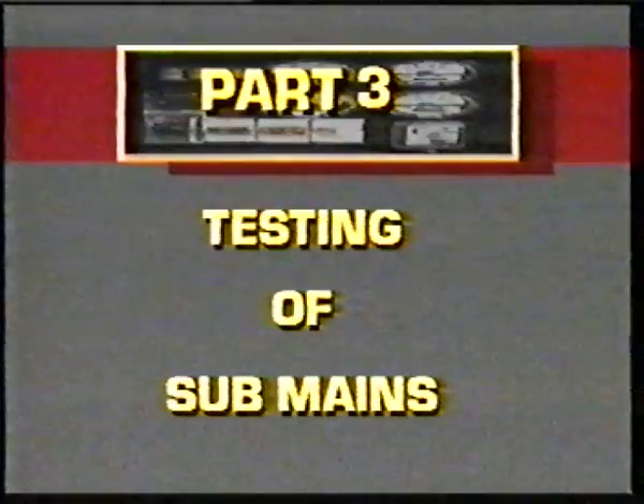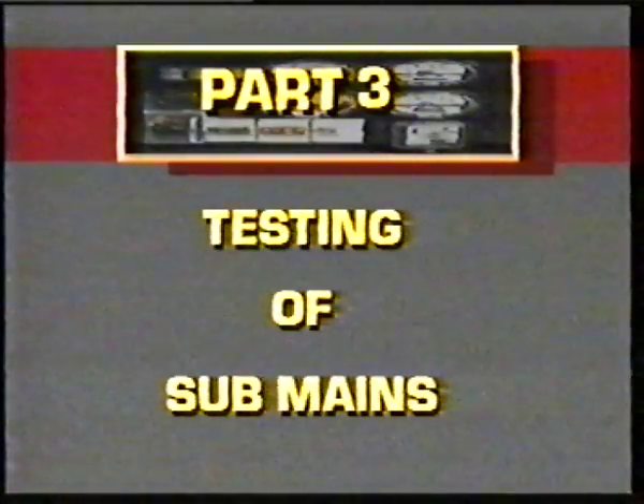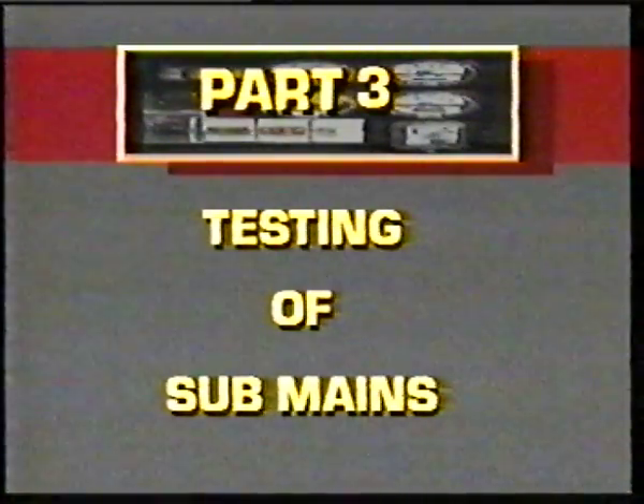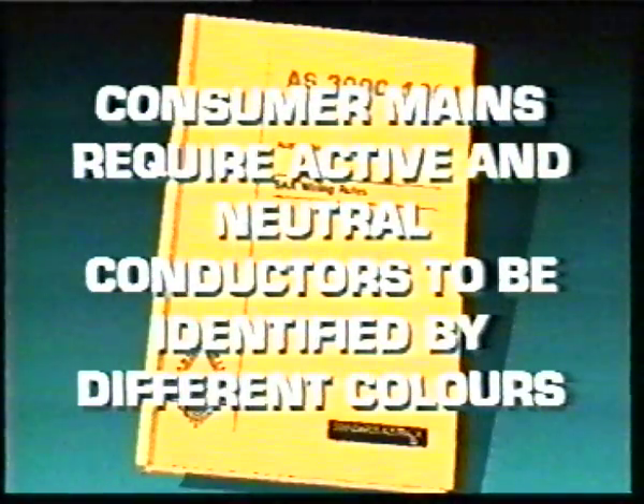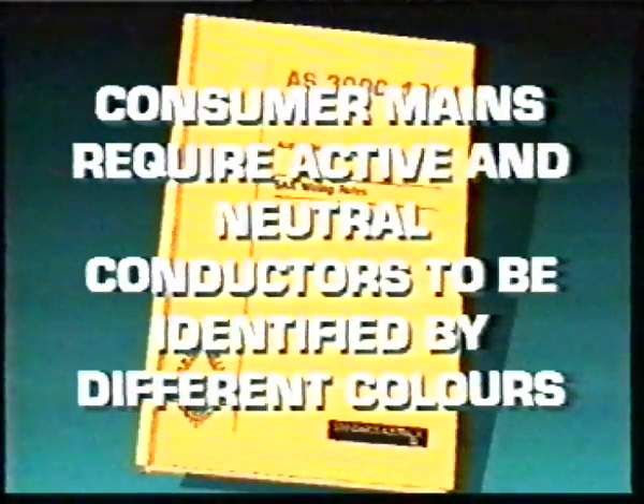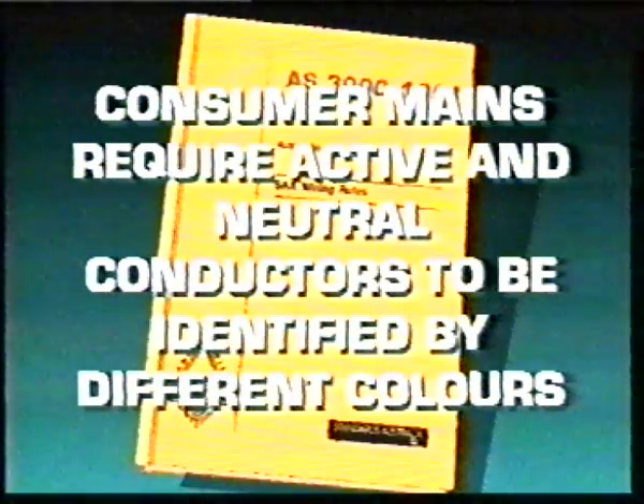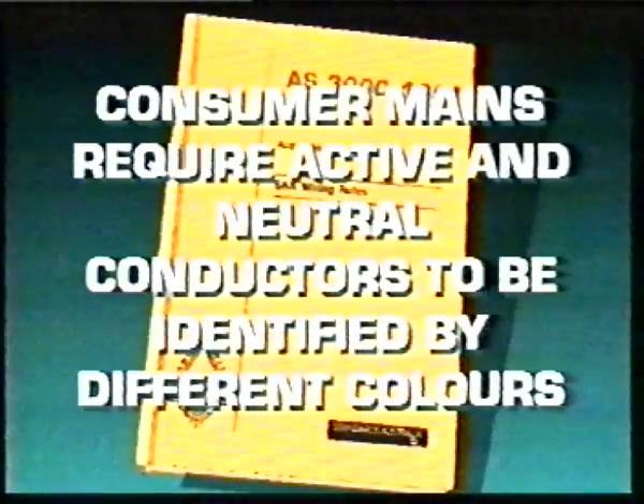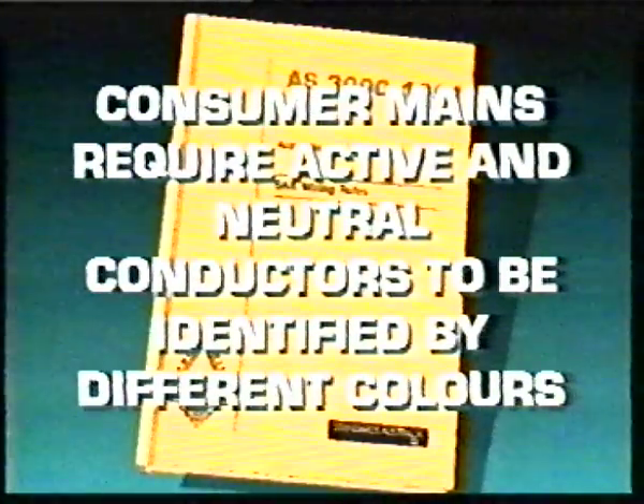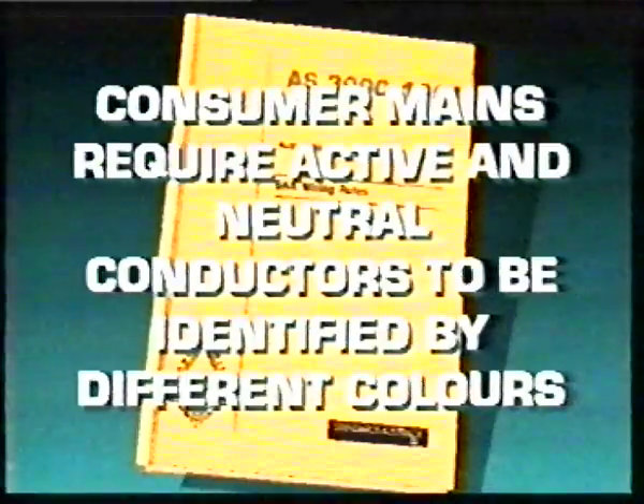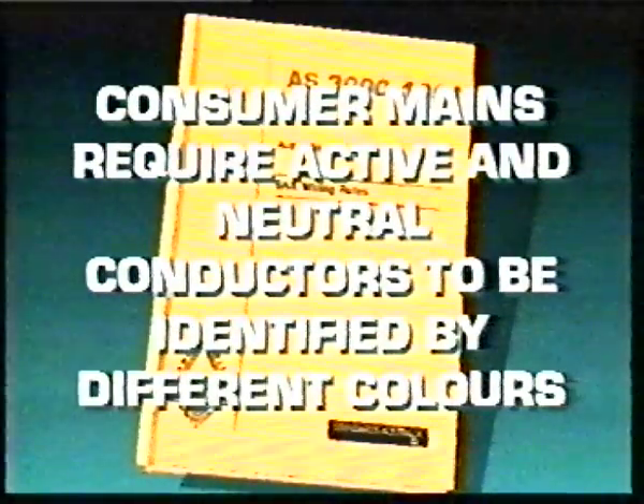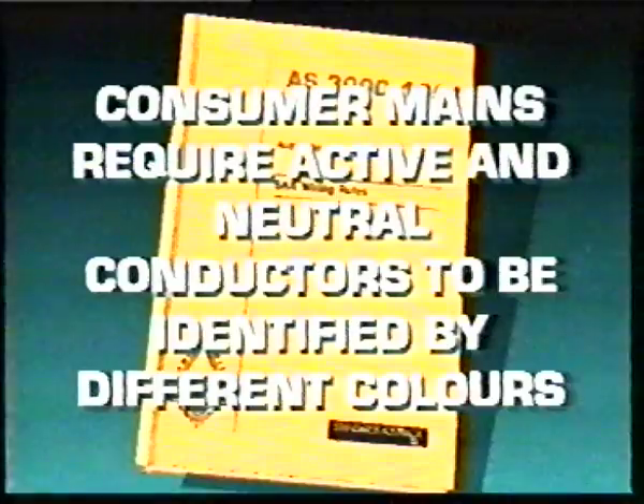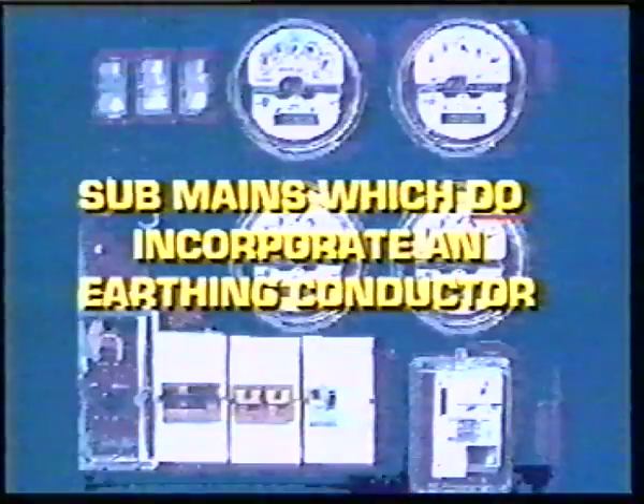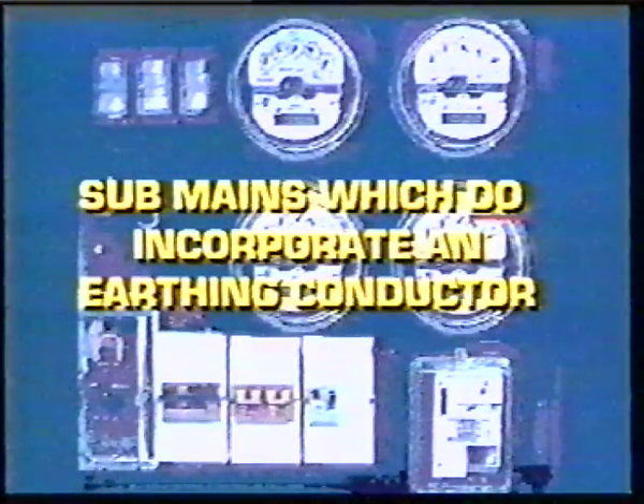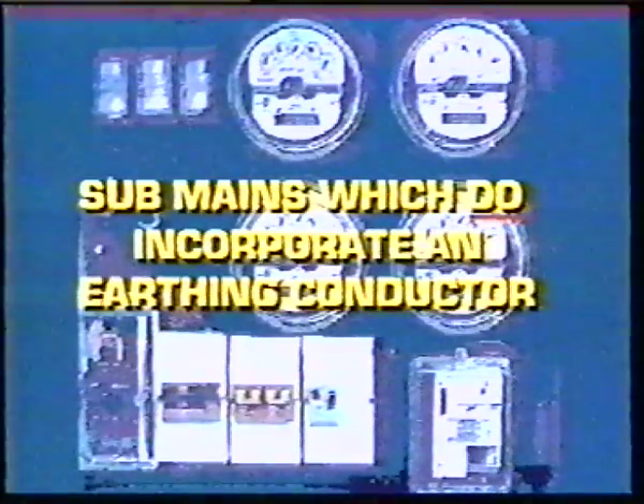The correct active-neutral connection of submain conductors is vital for the safety of an installation. AS 3000 recommends and, in situations regarding consumers' mains, requires that active and neutral conductors be identified by different colours. While this practice should reduce the likelihood of incorrect connection, polarity testing to ensure proper active and neutral relationships in submains is still considered to be essential. We'll first demonstrate the testing of submains which incorporate an earthing conductor.